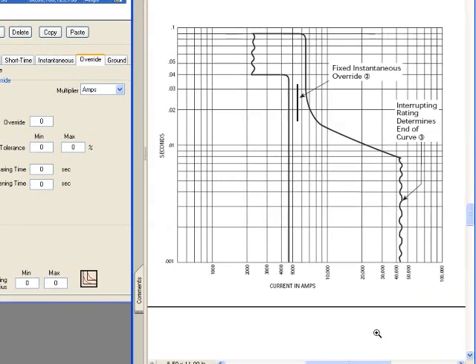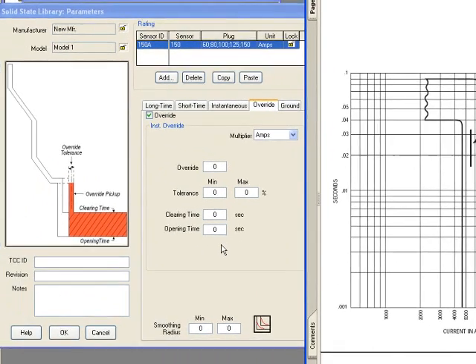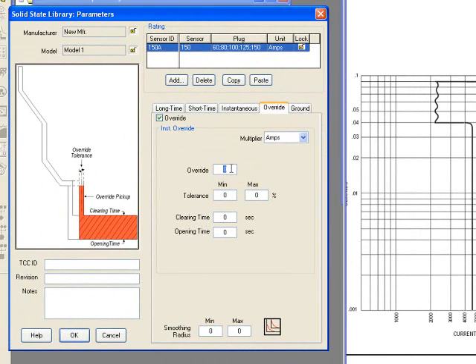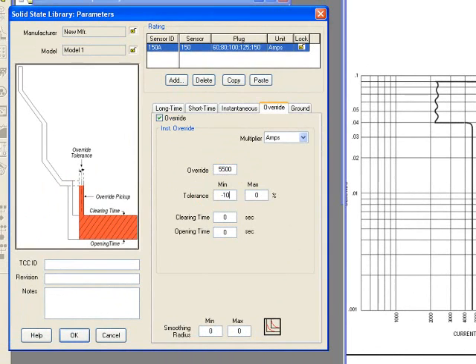For example, if you look at it with more detail of the case that is a fixed instantaneous override, and you need to address for what the pickup value, if not adjustable, is a fixed value, you have to select the pickup amps. Then you need to specify the tolerance in the same method, the minimum and the maximum tolerances.